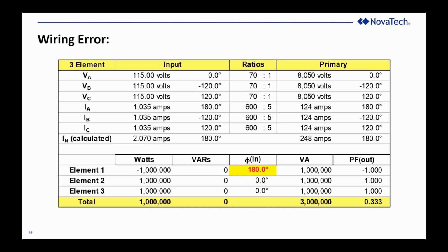The spreadsheet does the math, and the results are what you see below. So the resulting current, when you do the vector math between the three phase to neutral voltages, is about twice the per phase current. Like I said, that's not intuitive, but if you look at the vectors, it'll make sense. And the A phase watts is going to be basically exactly the opposite, the same magnitude with the opposite direction as the other two phases. You correct that, and you're back to business.